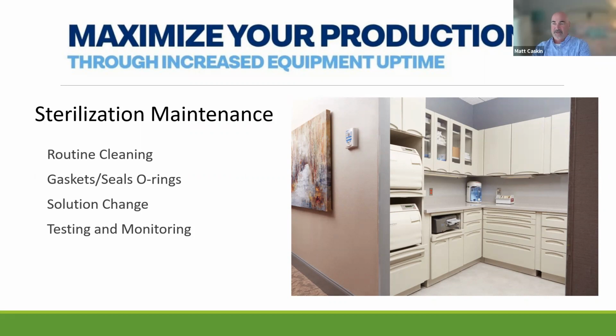And I also see what looks like a water distiller up on the counter. So another reminder, all of these machines require distilled water only. I can tell you, if you don't use distilled water, you will run into problems very quickly. The solenoids inside those machines will get gunked up and fail, and your sterilizers won't run. So it's very important to clean these on a regular basis and follow the manufacturer guidelines. I can tell you from prior experience, if you maintain this equipment and service it at the recommended intervals, it will run and run and run. They're workhorses. They work really well. They're very dependable, very reliable.